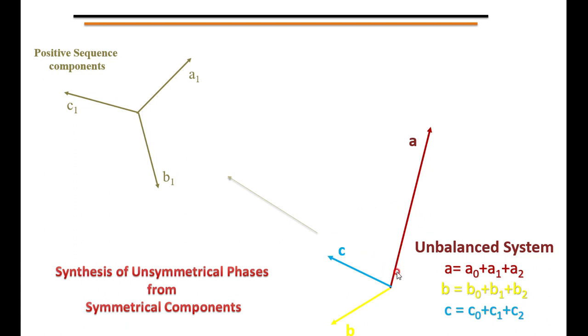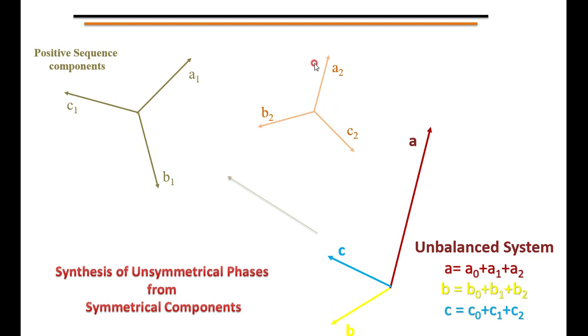The next component extracted from the unbalanced phasor is the negative sequence component — A2, B2, and C2. These are the negative sequence components of phases A, B, and C. Once again, A2, B2, C2 have equal magnitude and phase displacement of 120 degrees. But the phase sequence is opposite to the original: here it is A, C, B, whereas the original is A, B, C. This is what we call the negative sequence component.